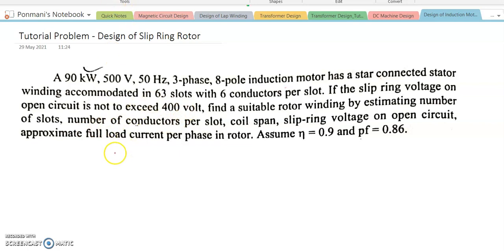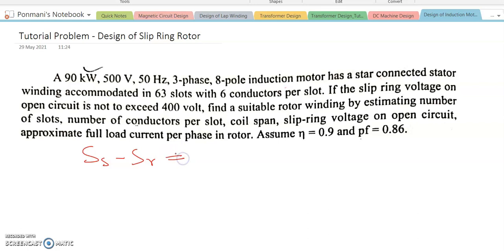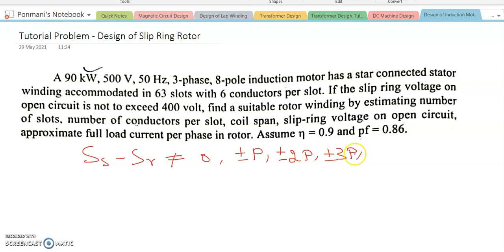To calculate the total number of rotor slots, we use the derived condition that the difference between stator slots SS and rotor slots SR should not be equal to 0, plus or minus p, plus or minus 2p, plus or minus 3p.